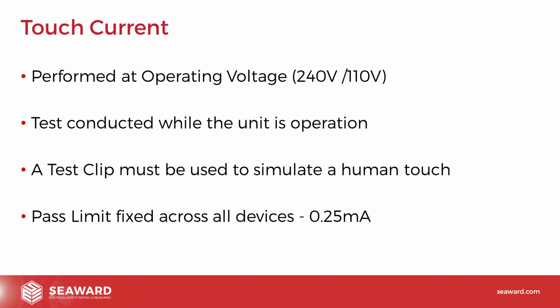Now, we call this a touch current test because essentially what we're doing is we're simulating the current that would flow through a human if they were to touch the device whilst it's in operation. So what we do is we apply a test clip or probe to the device to simulate a human touch. Essentially, we're putting a clip on the product to effectively act like a human. So if we were to touch that part of the product under test, what current would flow through our hand, i.e.